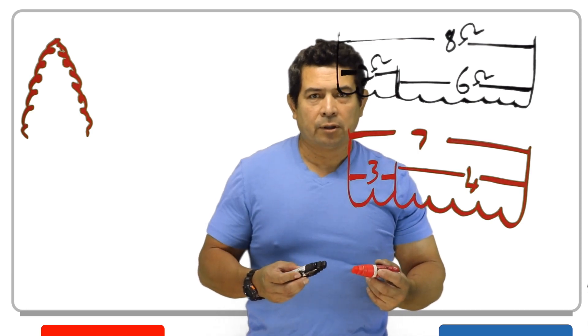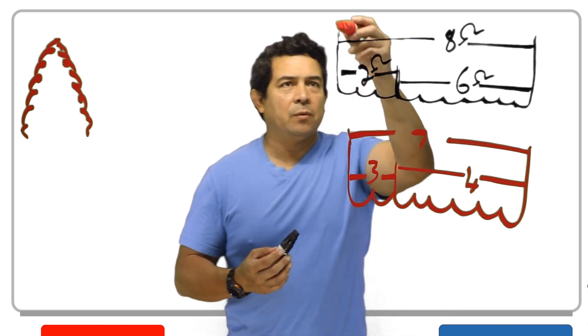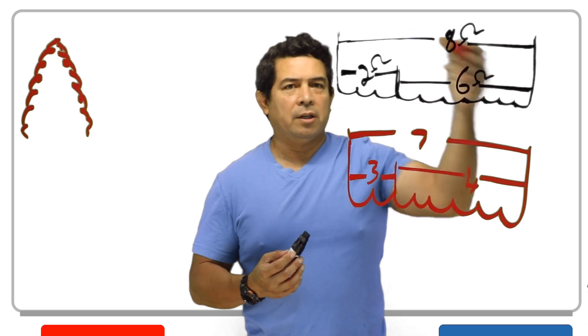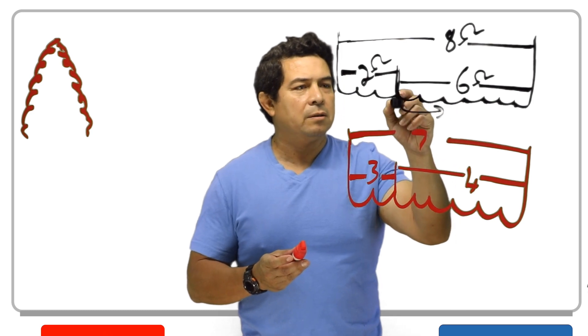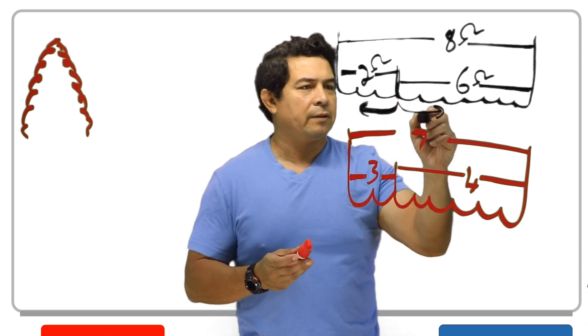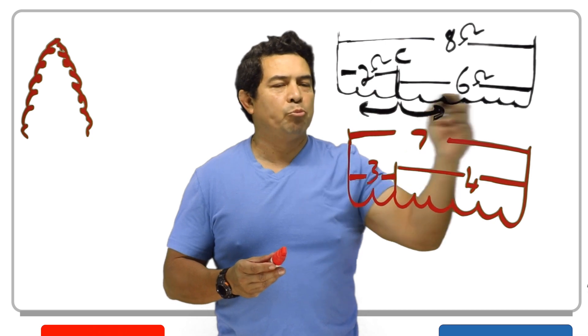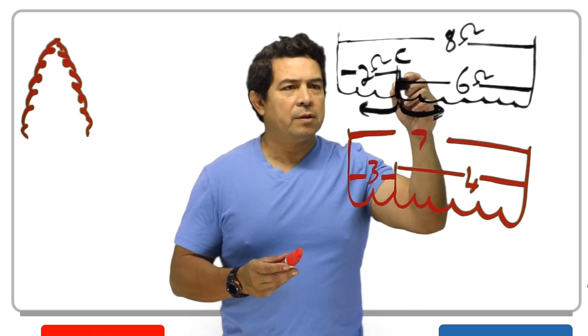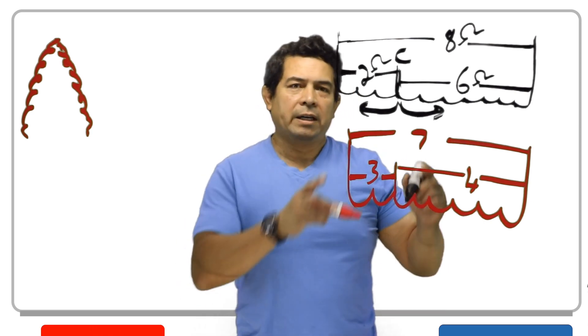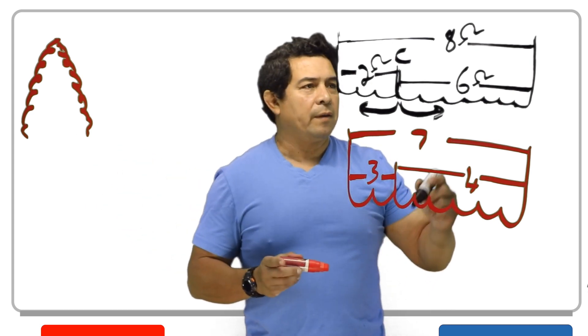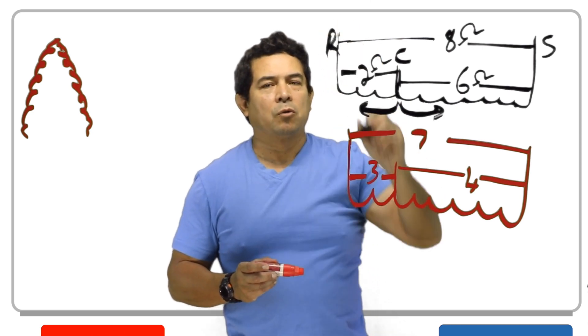Now let's look at how these two windings come together. We have connections on each end, and one in the middle. The one in the middle is connected to both windings, so we can say that this one is common to both windings. On a single-phase motor, one of those windings is going to be the start winding, and the other is going to be your run winding.